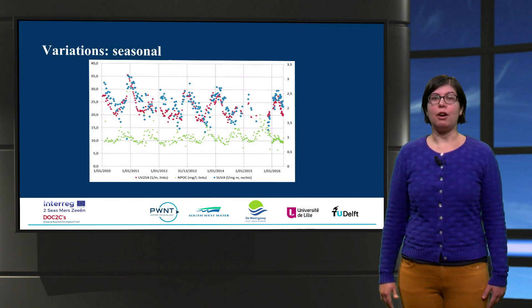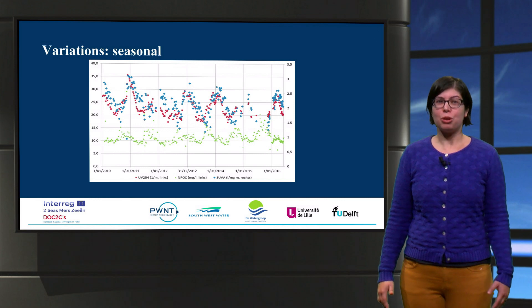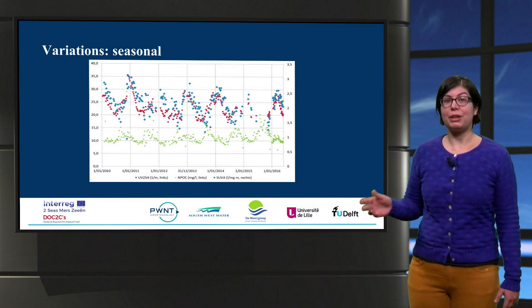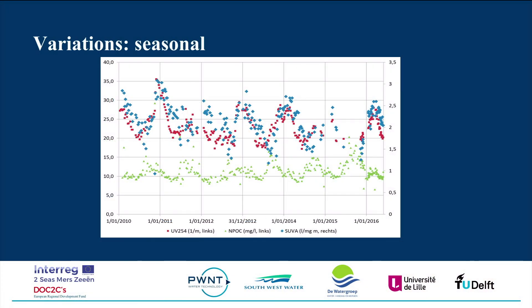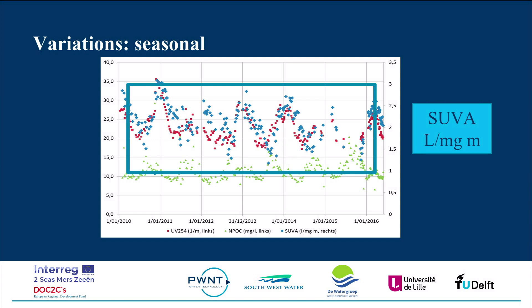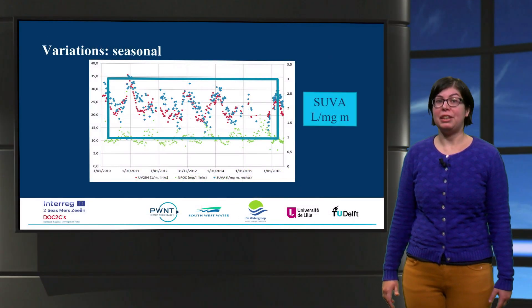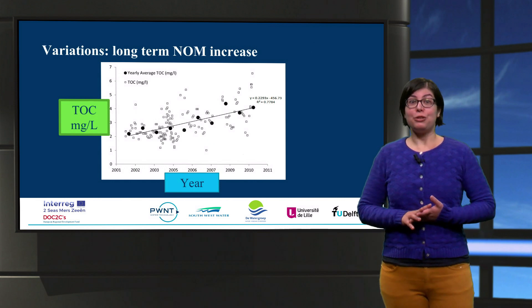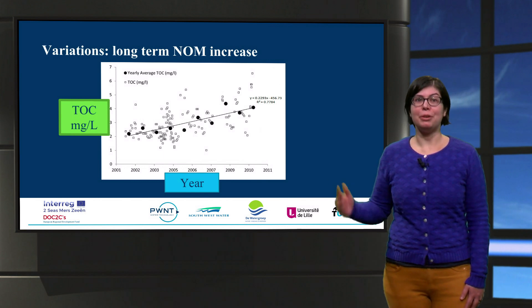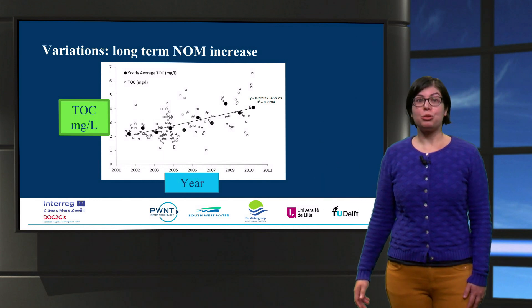Another issue is the variability of NOM in the water sources, which also creates challenges in how we remove NOM from water. In the graph of this example, the horizontal axis gives the time and the vertical axis gives the measured NOM parameters. If we look at the concentration of dissolved organic carbon, here in mg per liter, we see that there are seasonal peaks. Not only the concentration but also the character of the NOM may change seasonally, as illustrated by the variation of the SUVA value. In Northern European sites, variation in NOM has been observed on a broader time scale as well, with NOM concentration seeming to increase over the years.